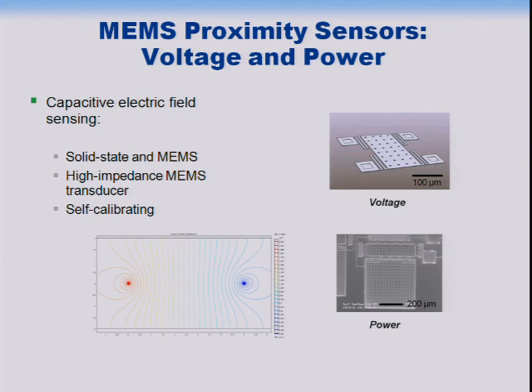By looking at the gradient, the differences between several of these points where we measure the field, and if we know some of the geometry of the wire, we can calibrate the sensor automatically because we know what the gradient should be. This shows the field between two neighboring conductors.